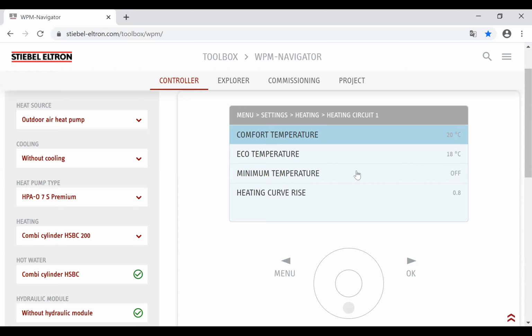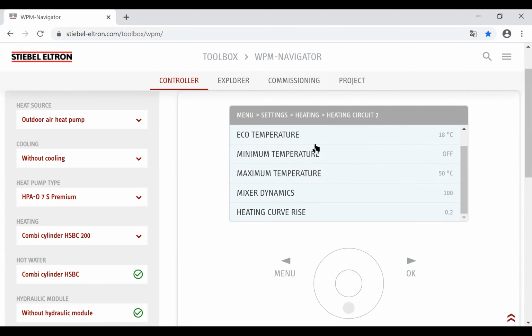Let's pop back into heating circuit 2. Heating circuit 2, remember, is the first of our mixed circuits. Because we have a mixer on this circuit, we can set our comfort temperature and eco temperature. So comfort temperature might be a daytime and evening temperature, and eco temperature might be overnight. And then we use the program to jump between them. Having a mixer, all of a sudden we can set up a maximum temperature. We can set up a mixer dynamics, meaning the speed at which the mixer is operating. So we can use other mixers that aren't necessarily supplied in our standard product range. And once again, we can set a particular heating curve for heating circuit number 2. Now, we can keep going there. We can keep expanding on that.